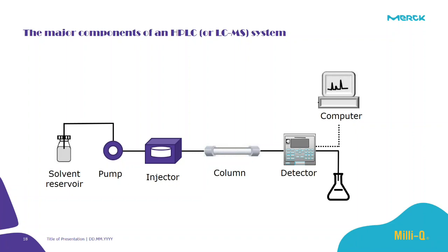So first of all, we have the solvent in the reservoir, and then the pump will take the solvent through the injector to pass through the column, and then finally to the detector. So where can problems occur exactly? For sure, the pump can be affected, the injector can be affected, the column can be damaged, and also the detector.